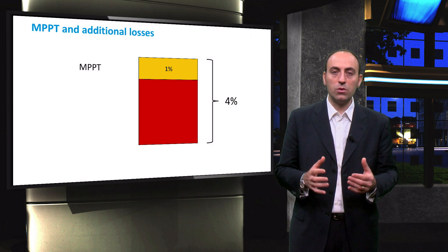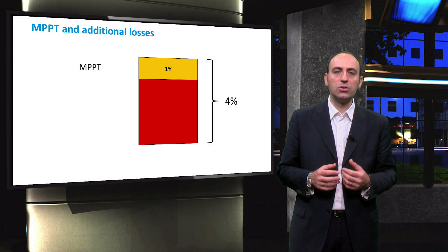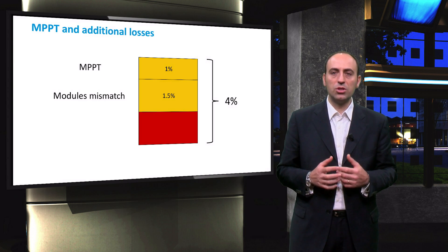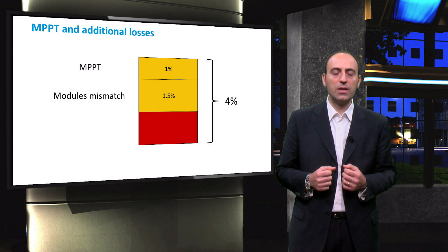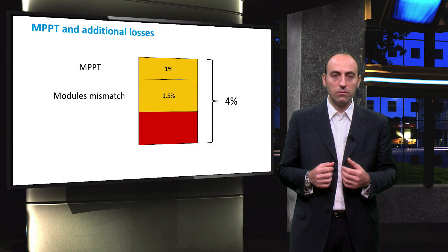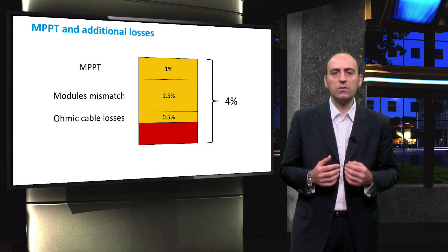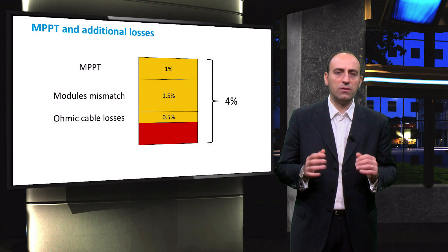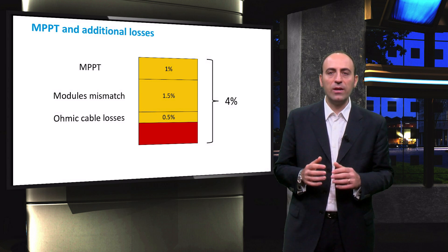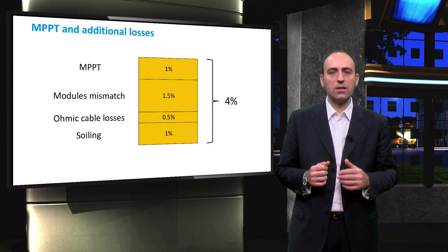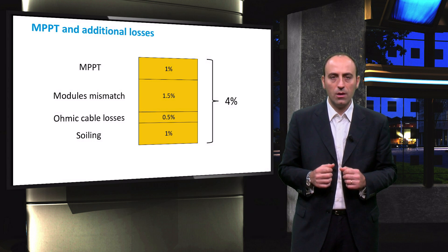Among the other losses worth mentioning, we can mention the mismatch between modules, which accounts for roughly 1.5%, ohmic losses related to external cabling of the inverter, usually considered to be around 0.5% if not determined analytically, and finally, soiling losses as an additional loss of 1%.